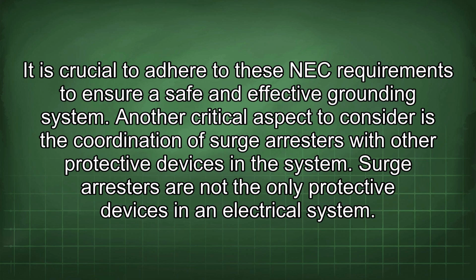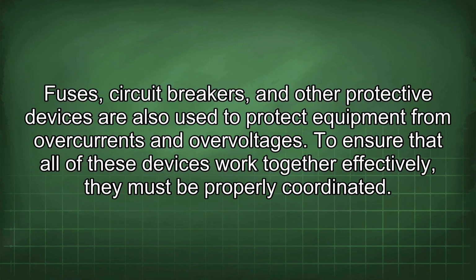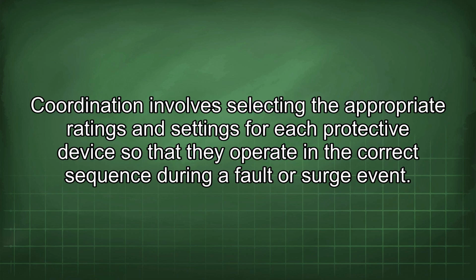Another critical aspect to consider is the coordination of surge arrestors with other protective devices in the system. Surge arrestors are not the only protective devices in an electrical system. Fuses, circuit breakers, and other protective devices are also used to protect equipment from overcurrents and overvoltages. To ensure that all of these devices work together effectively, they must be properly coordinated. Coordination involves selecting the appropriate ratings and settings for each protective device so that they operate in the correct sequence during a fault or surge event.